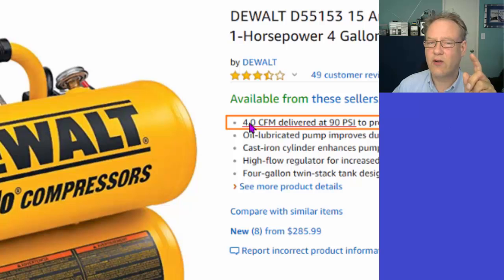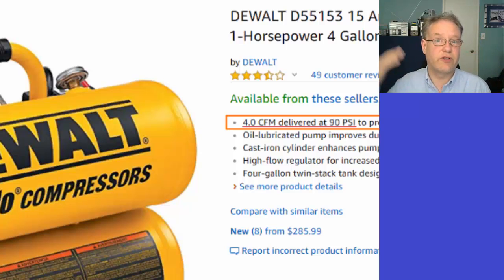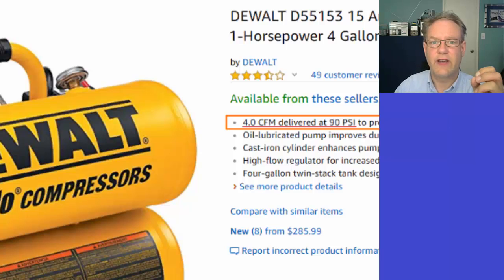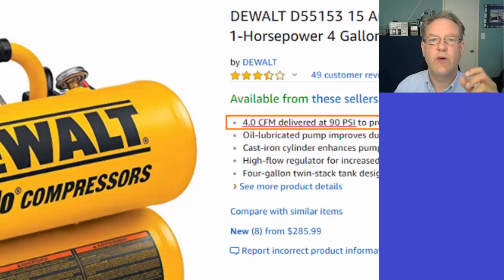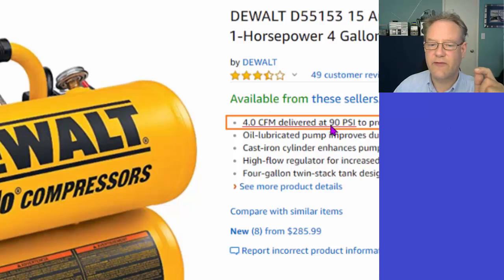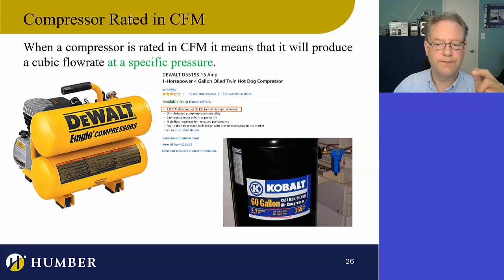If I kick the pressure down to 45, does the flow rate go to 8? The answer is no. You'd think so because these things are relative to each other, but my pressure is not actually halving — we have to deal with absolute pressures. So taking it from 90 to 45 PSI gauge doesn't double the flow rate; it probably goes to about 6.8 or 7.